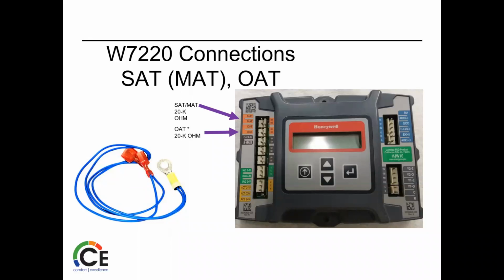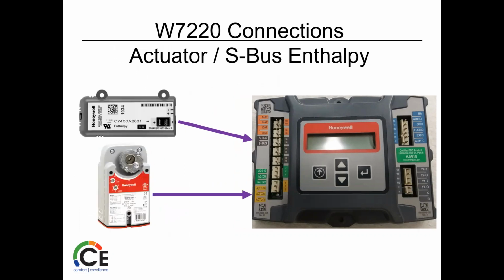So again, if we have a basic SAT or MAT control, there's a spot clearly labeled where that goes. Your outdoor ambient clearly labeled where that goes. If you're using the newer style enthalpy, you can't put that on MAT or OAT. That has to go on the S bus terminal. Different communication way, different sensor. There's been a lot of times where we put it where the OAT used to be. It will not work. It has to be on S bus. And then, of course, your actuator down the bottom has its own spot to go to.